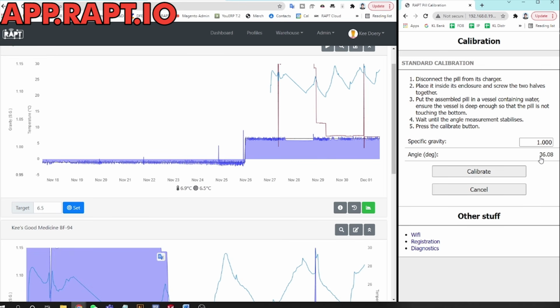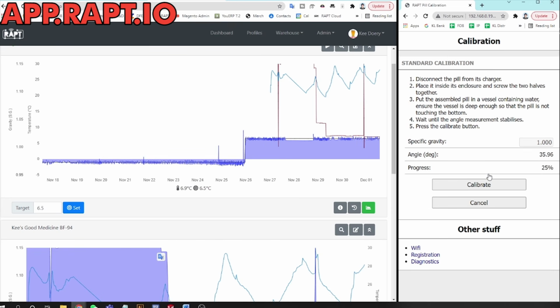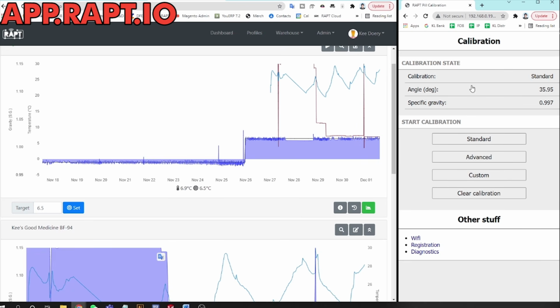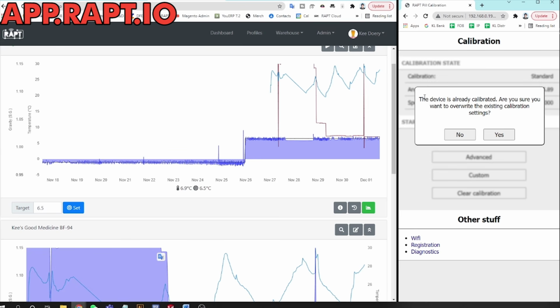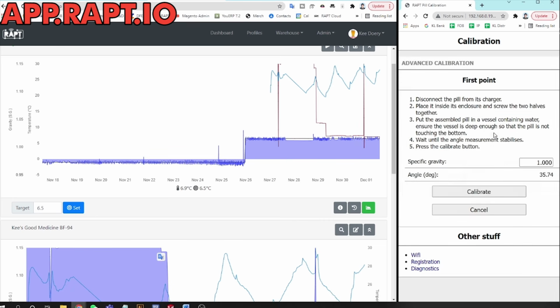And once you know this angle has stabilized and it's not accelerating in any particular direction, hit the calibrate button, and then the progress will go from 0 to 100%. As you can see, it doesn't take too long. It's basically feeding the information back up and writing this change to the actual board itself and saving it in the firmware. Now, if you want a more complex calibration, you can go into advanced calibration mode. If I click on this, you'll see, now, look, advanced calibration is not absolutely necessary, I should say. For most people, it's going to give you quite accurate readings anyway. So only go into this if you really can be bothered, but click on yes to go into advanced.